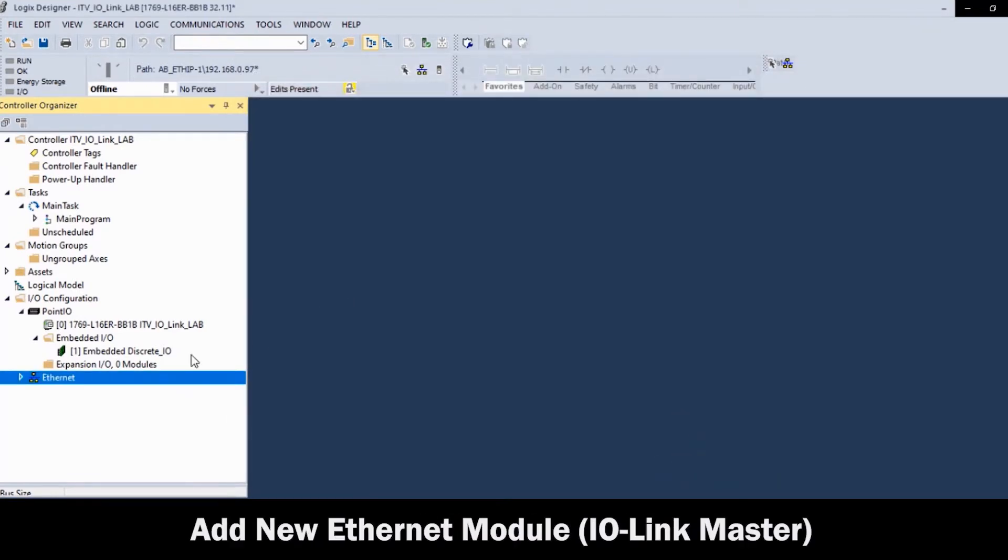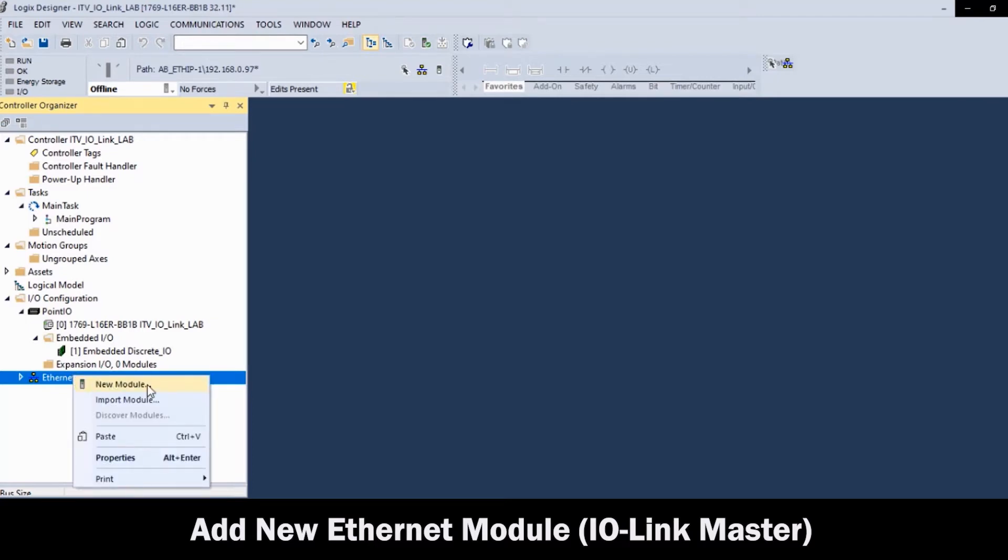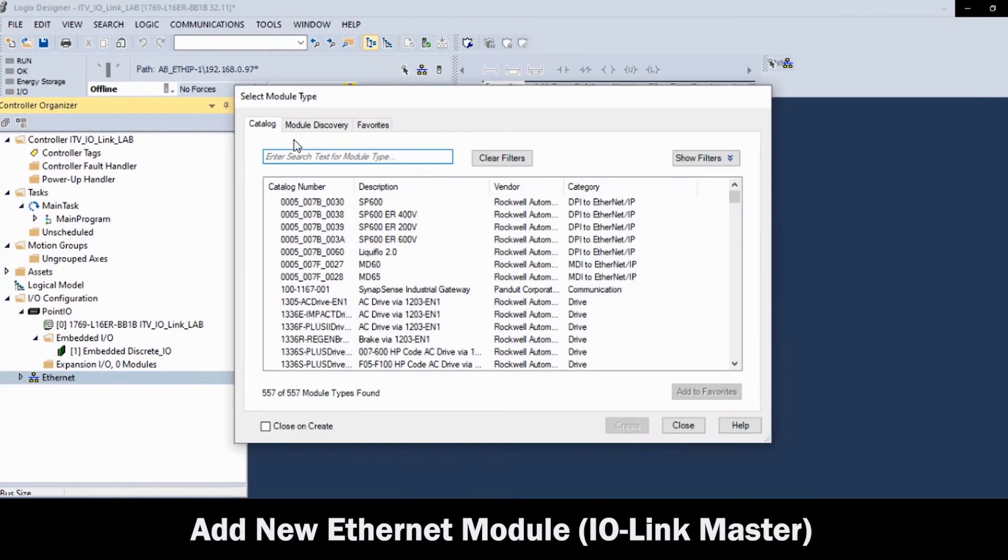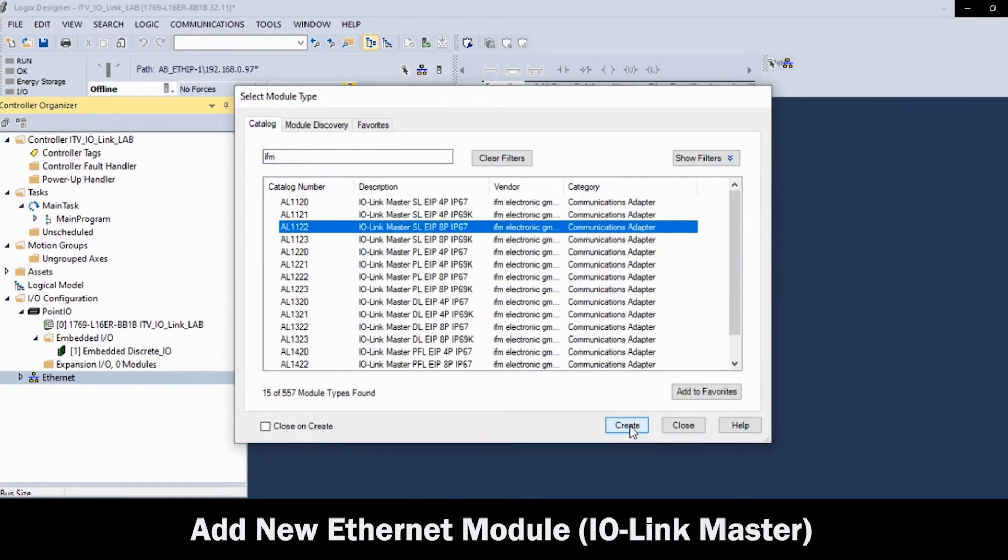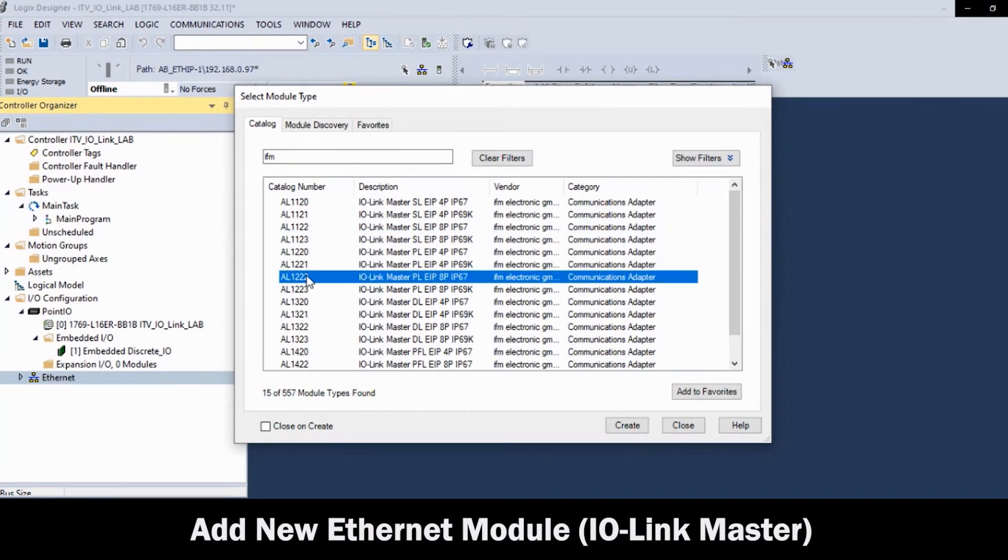Right-click on the Ethernet scanner in the controller organizer and select New Module. Isolate and select the ifm IO-Link Master brand. Then, in the Select Module Type table, highlight the IO-Link Master model and click Create.